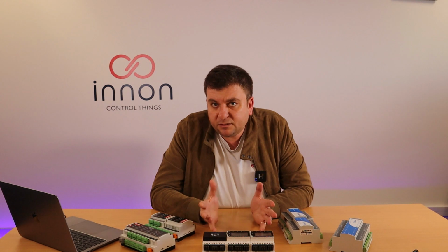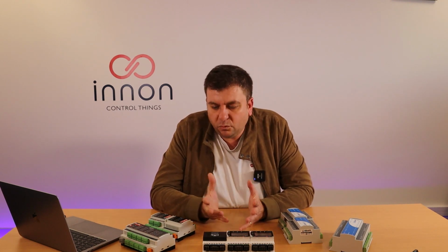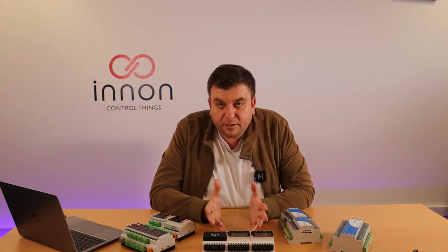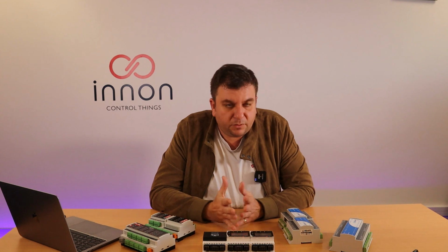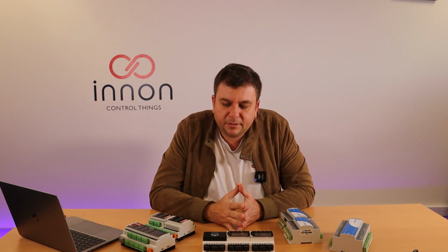About the protocol itself, I think Modbus is pretty well established. So I can comfortably say if you've got a Modbus device, you can pretty much connect it to any building automation system. All the three products on the table here have Modbus. Two of them have BACnet, which is quite popular all over the world now.